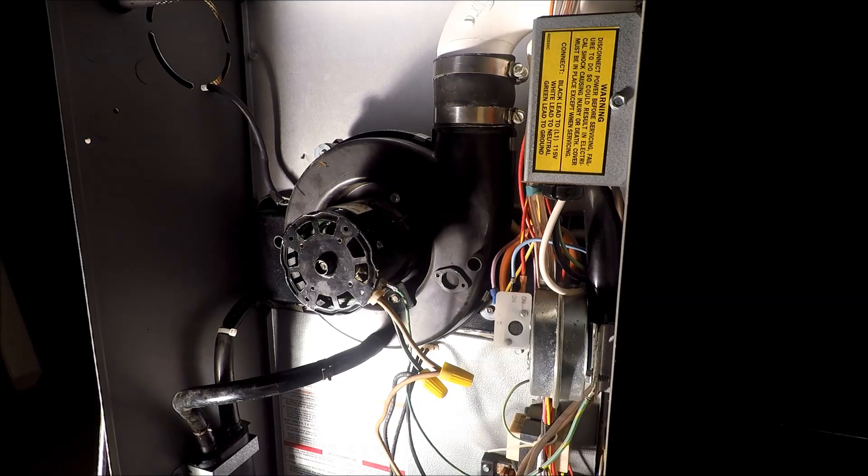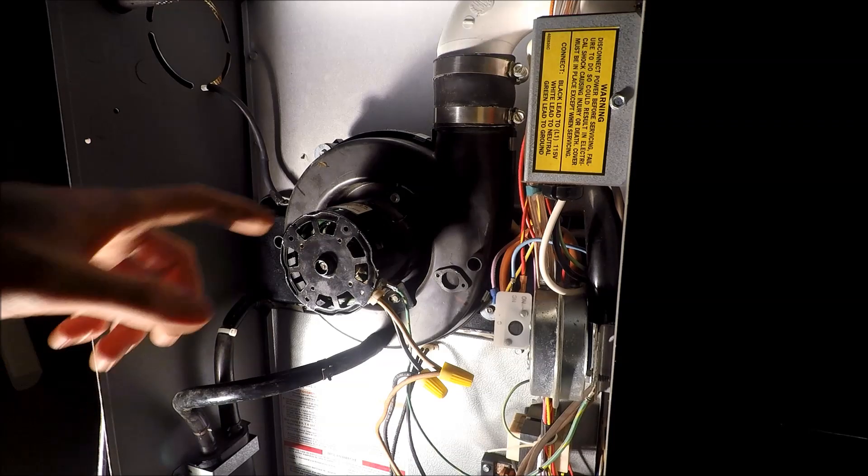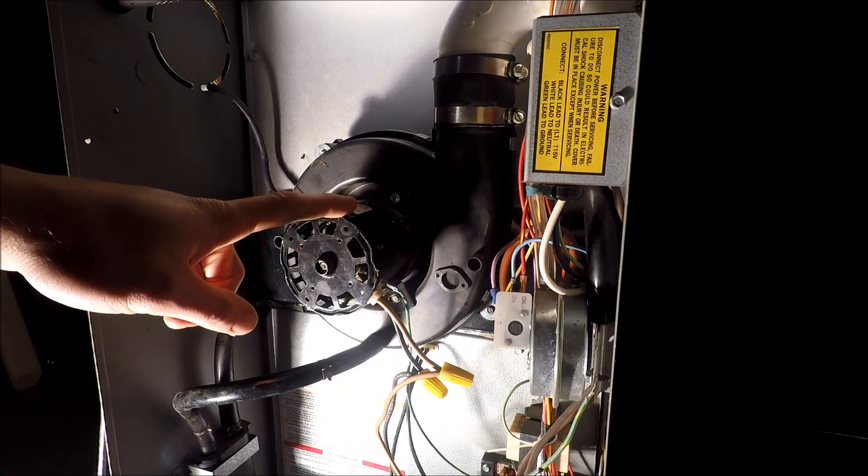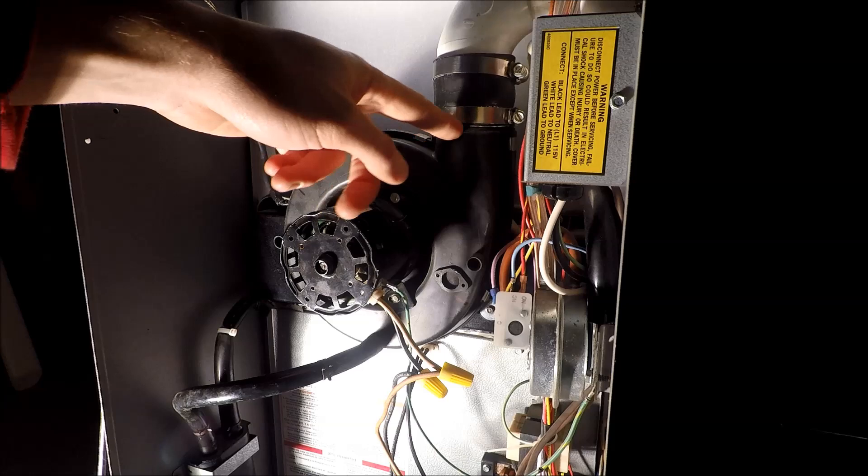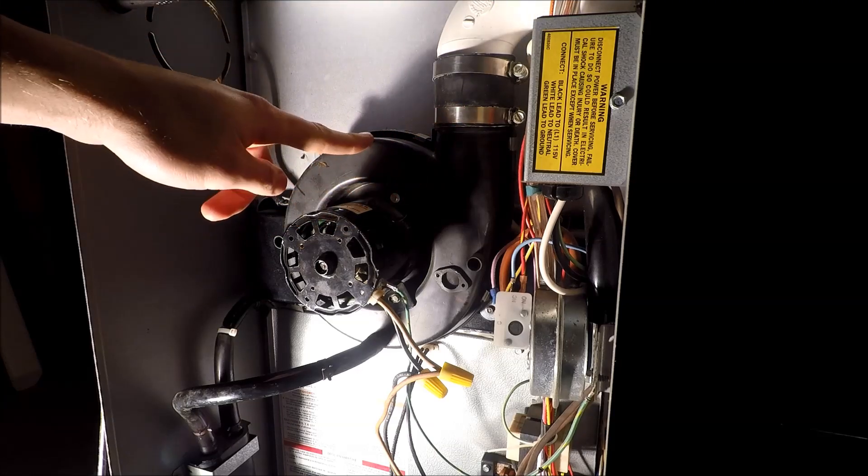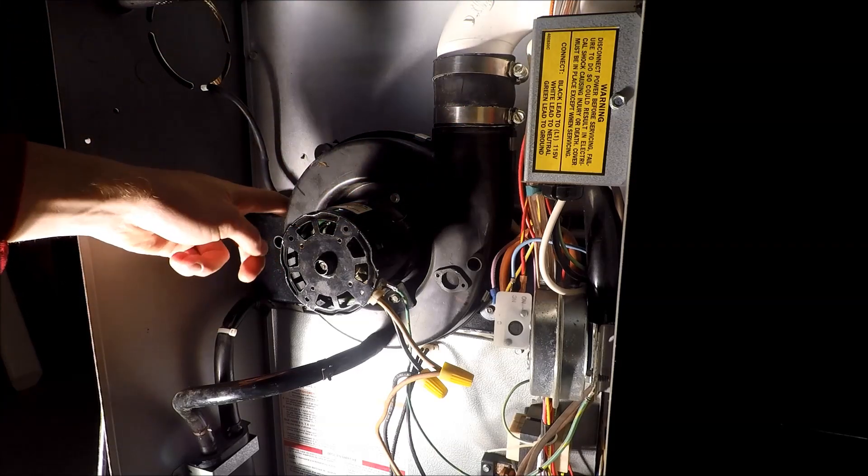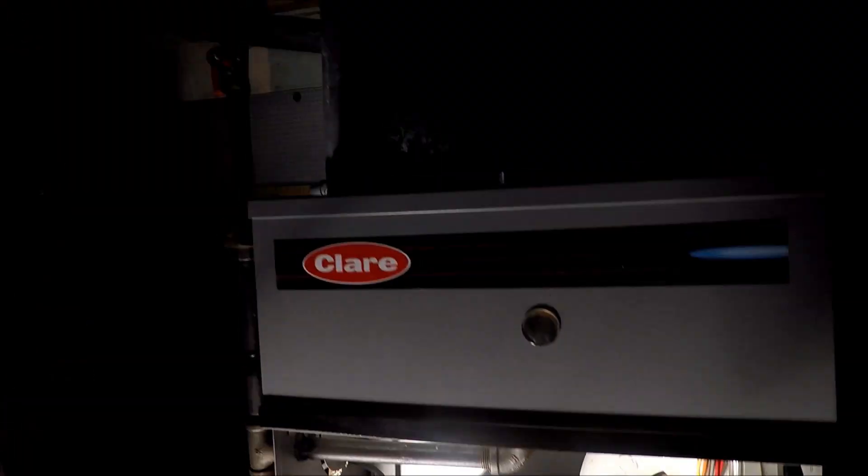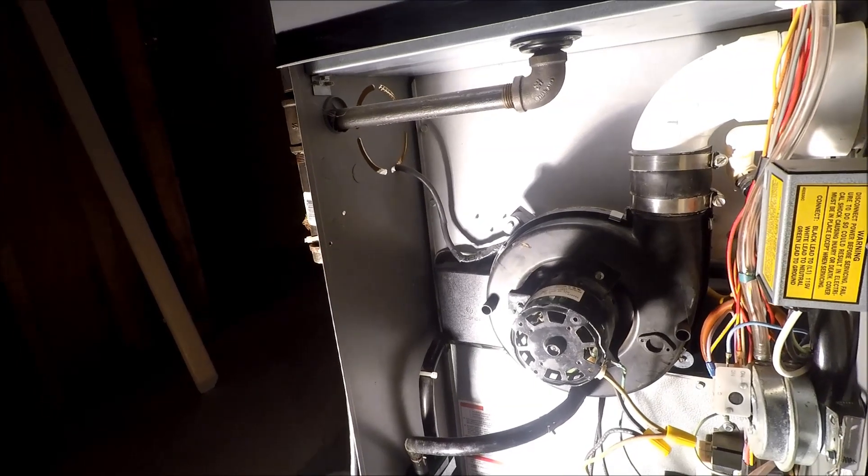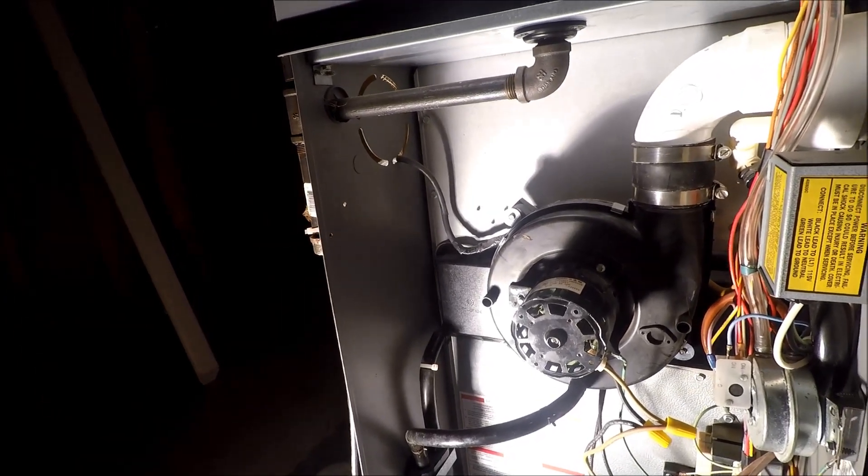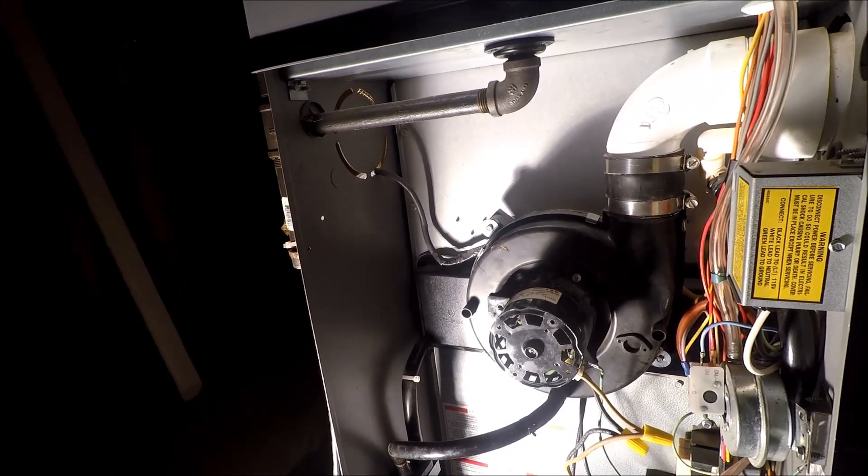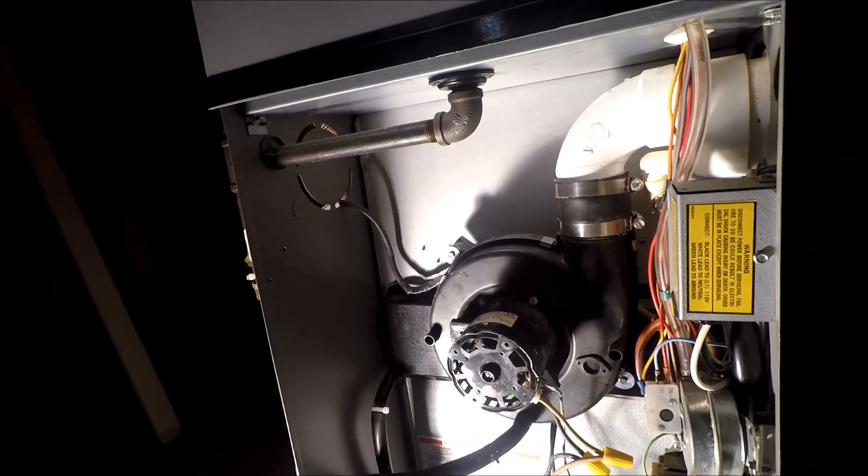If your furnace sounds like that, then you got a problem with this draft inducer motor right here. It's pretty much blowing your exhaust fumes out and sucking in gases and blows them out. This is a Clare, so it's an older model furnace. My documentation shows that I think it was upgraded in 1997, so it was installed before then.